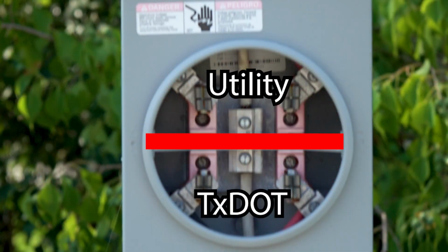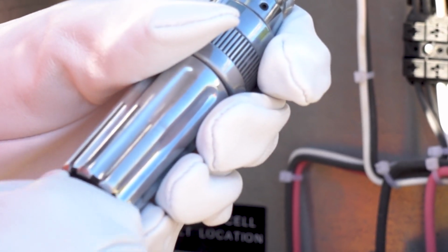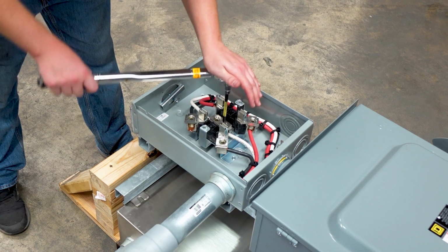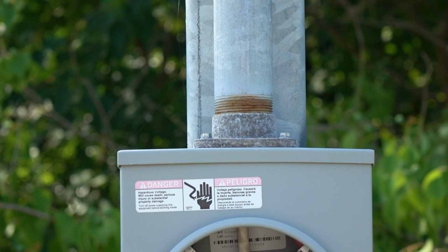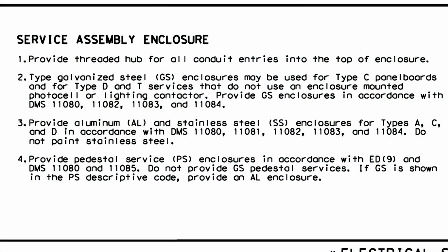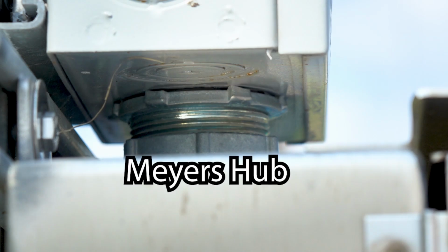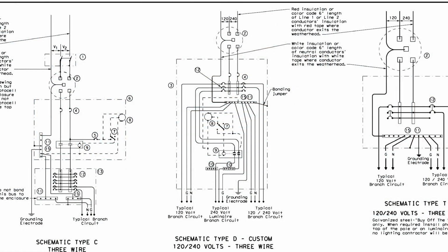The inspector will need to visually confirm that all of the conductor strands are under the retaining lugs and properly torqued. The utility company will confirm proper torque of the top 3 conductors. The inspector should confirm that the 3 lower conductors have been properly torqued. This item may not be able to be checked if the meter is already installed. The torque wrench for this inspection task is to be provided and operated by the installing contractor. The NEC requires that electrical enclosures located outdoors have conduits installed in such a manner that water will not enter the enclosure. TxDOT requires that either a threaded meter hub or a Myers hub be used for these types of conduit to enclosure connections. Let's now review the schematic drawing found on ED6.